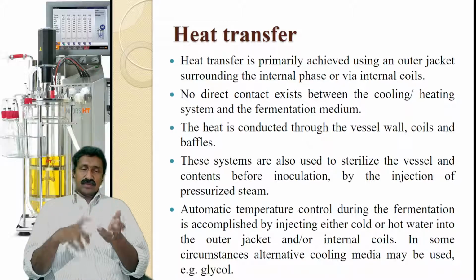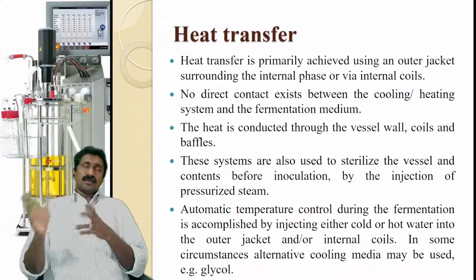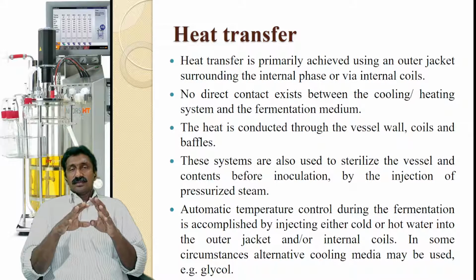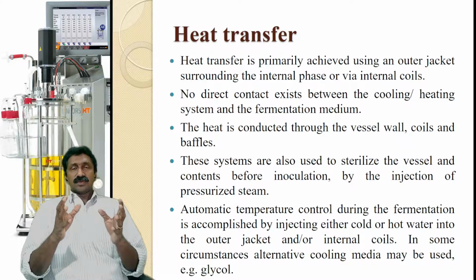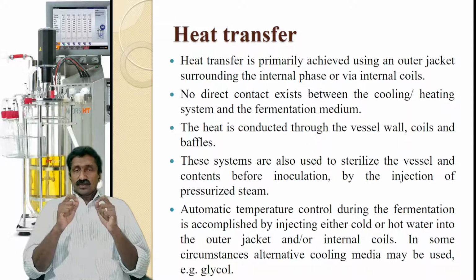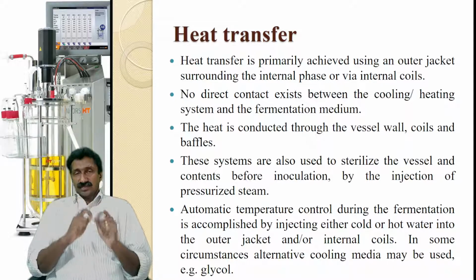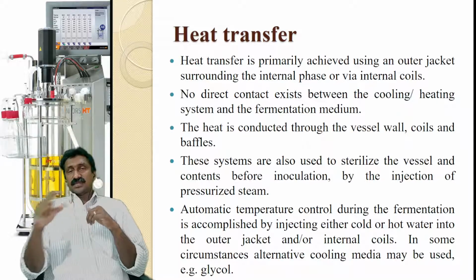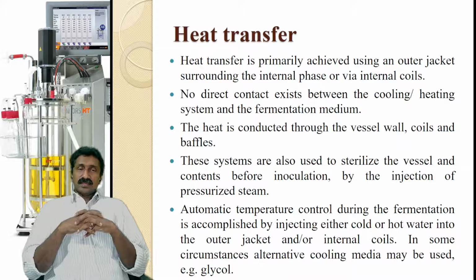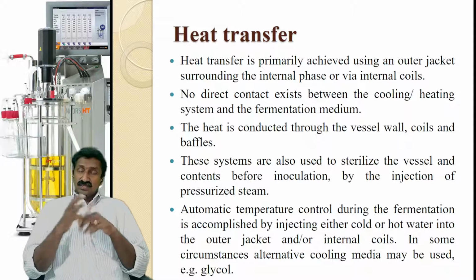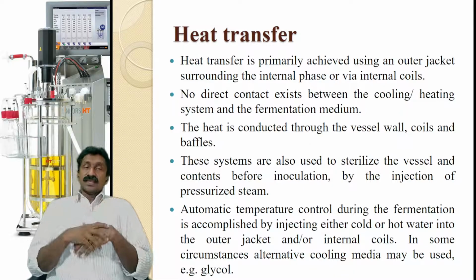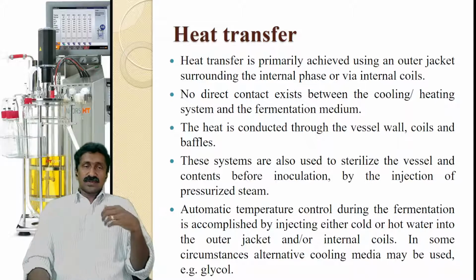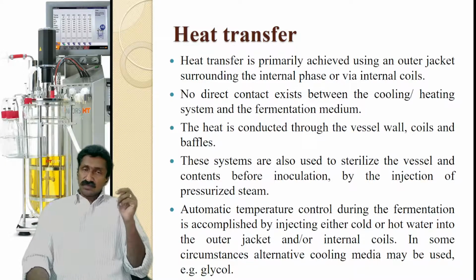And even during the process of sterilization, and also during the process of fermentation, there is no direct contact allowed, so that contamination possibilities can be minimized. So it is not through direct contact, but through the conductive process of heat transfer through the jacket walls and the walls of the internal pipes that heat is actually transferred. And in some circumstances, alternative cooling media may be used. Instead of water-cooled systems, we can also use, say, glycol, which may ensure better heat transfer efficiency. So additional heat transfer cooling systems can also be used.